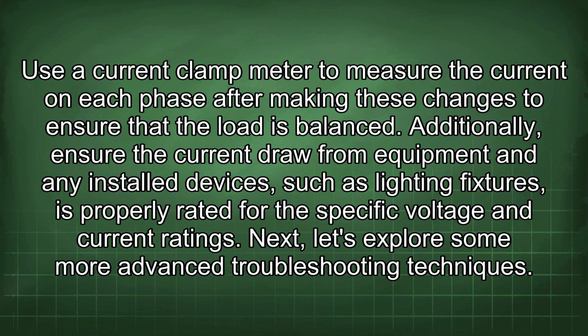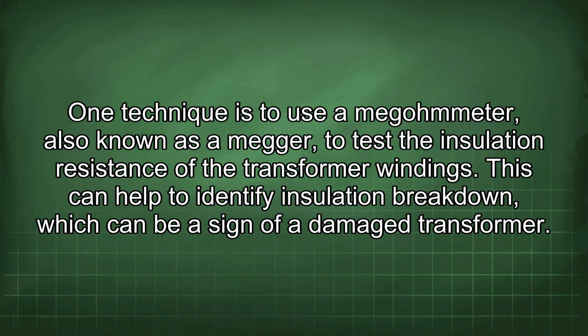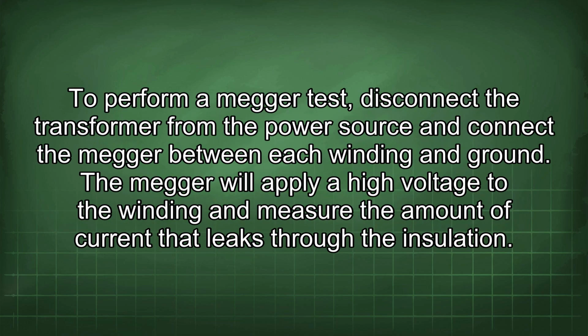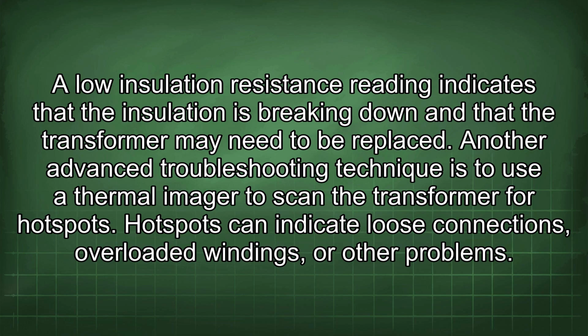Next, let's explore some more advanced troubleshooting techniques. One technique is to use a megohmmeter, also known as a megger, to test the insulation resistance of the transformer windings. This can help to identify insulation breakdown, which can be a sign of a damaged transformer. To perform a megger test, disconnect the transformer from the power source and connect the megger between each winding and ground. The megger will apply a high voltage to the winding and measure the amount of current that leaks through the insulation.